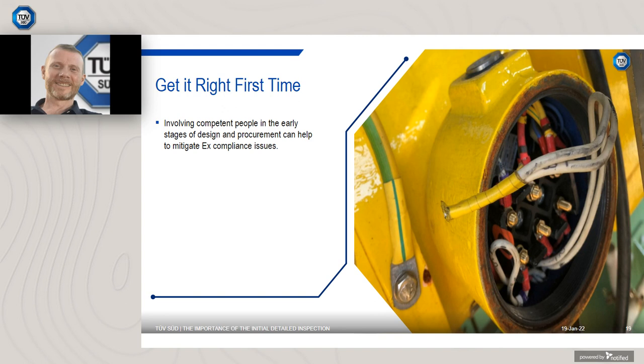Some simple checks prior to the install would have mitigated the additional scopes of replacing a full new cable. A competent designer would ensure that the cable supplied had the correct number of cores. A competent installer would have queried the additional cable cores and not just taped them up, hoping no one would notice.